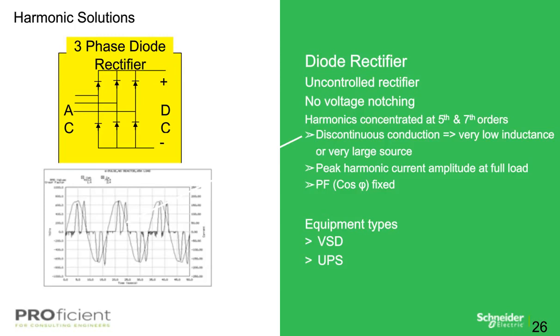Higher orders of harmonics occur when there is no or very low inductance at the rectifier, either AC or DC side. As shown above, lack of inductive impedance causes very large amplitudes at higher harmonic orders. Typically, you see this in devices like a UPS or a VFD. And as you can see in the chart, there are substantial drops within the graph below.